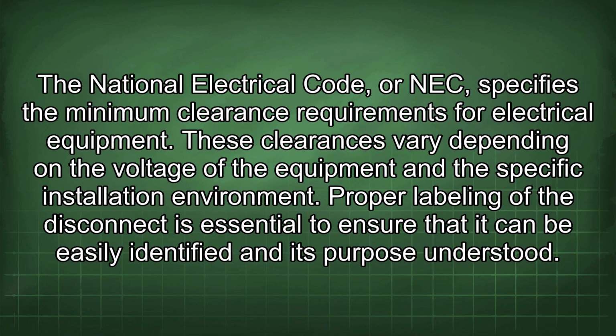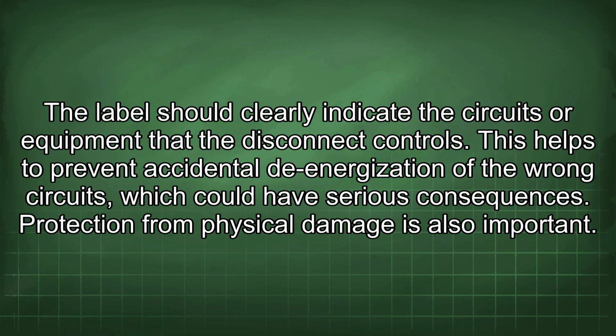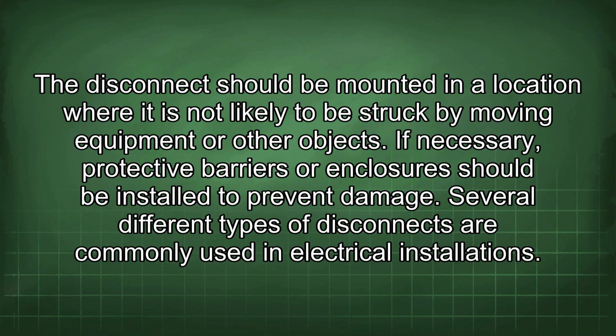Proper labeling of the disconnect is essential to ensure that it can be easily identified and its purpose understood. The label should clearly indicate the circuits or equipment that the disconnect controls. This helps to prevent accidental de-energization of the wrong circuits, which could have serious consequences. Protection from physical damage is also important. The disconnect should be mounted in a location where it is not likely to be struck by moving equipment or other objects. If necessary, protective barriers or enclosures should be installed to prevent damage.